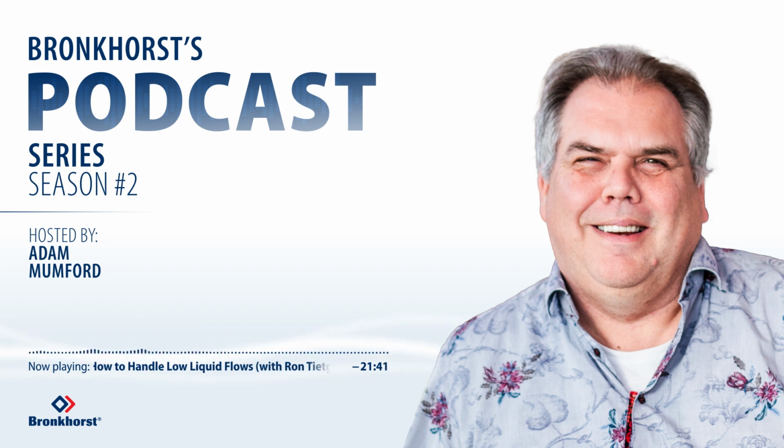So before going deeper into the topic with Ron on how to handle a low liquid flow, let's start with the basics. Ron, what is a low liquid flow? That's a good question, Adam. It's a pleasure to be here, of course, and talk about low liquid flows. It all depends in which industry you are. In the bulk industry, for example, 500 kilogram per hour is already considered low flow. In research, it's a lot lower. Every year they develop literally millions of new liquids, and the ingredients used are often very, very expensive. Therefore, a flow like 100 grams an hour is considered low flow, and everything less than 5 grams per hour is considered ultra low flow.